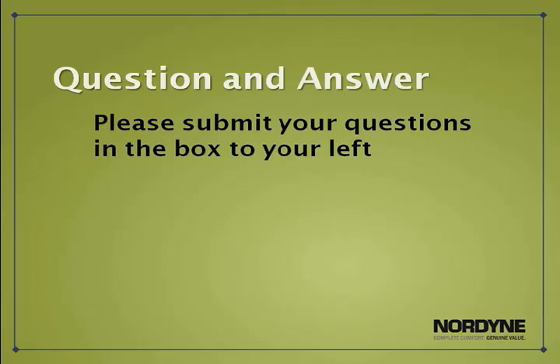It's not timed, I'll put it that way. It's not strictly just a timed feature, I guess. Maybe that was the better way to answer the question. Yeah, it's our standard adaptive demand defrost cycle. It's similar to what we're using with the IQ drive. Kind of the same steps. You still go through the pre-defrost, then the defrost mode, and then determining the temperatures afterwards when we've got the clear coil temperature stage on it.